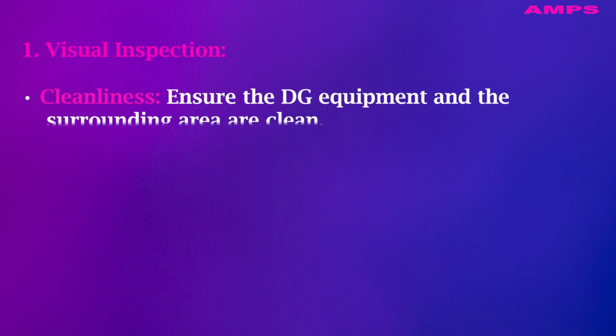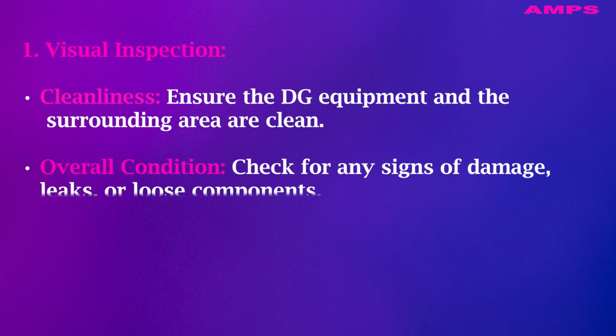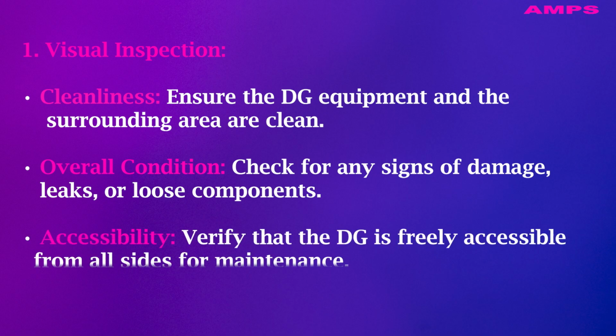1. Visual inspection. Cleanliness: ensure the DG equipment and the surrounding area are clean. Overall condition: check for any signs of damage, leaks, or loose components. Accessibility: verify that the DG is freely accessible from all sides for maintenance.